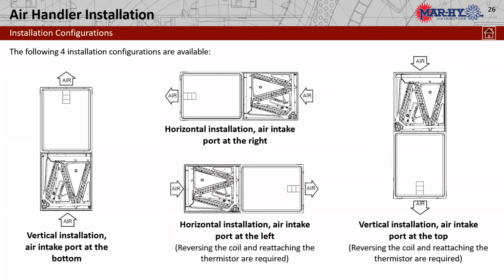Now, as with our standard air handler, you may have to swap the coil. You may have to orient the coil differently to make sure we get the right input on the air, to keep the condensate on the bottom of the unit, regardless of whether it's downflow, upflow, or horizontal. So again, look at the knockouts that are available. Depending on which way the airflow goes, we may need to relocate that return air sensor, and it needs to be upstream of the coil. Always keep that in mind. If you're upflow or horizontal left, you won't have to make any changes. The only changes on that sensor would be if you were downflow or horizontal right.